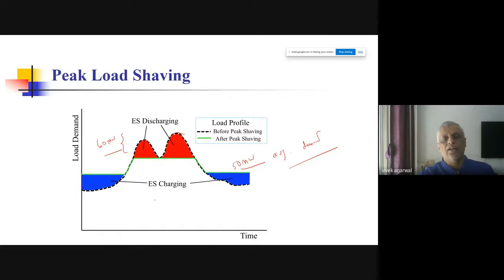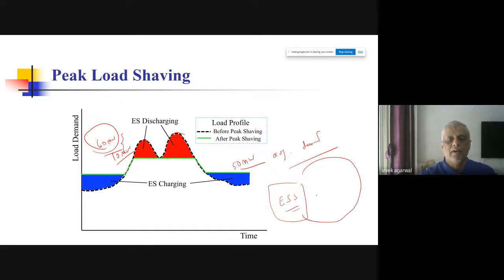So if you have energy storage in your system, instead of expanding our infrastructure to handle 60 megawatts, we can have a 10 megawatt energy storage system in our microgrid. And it can provide that 10 megawatt of balancing power. The remaining 50 megawatts is coming from the microgrid anyway. So as far as the microgrid is concerned, you don't have to upgrade its infrastructure to 60 megawatt. That would be much more expensive than just using this small difference, the 10 megawatt system, inserted here.